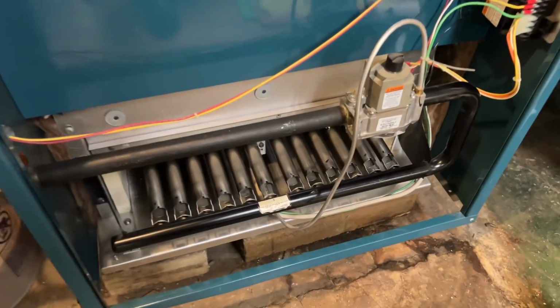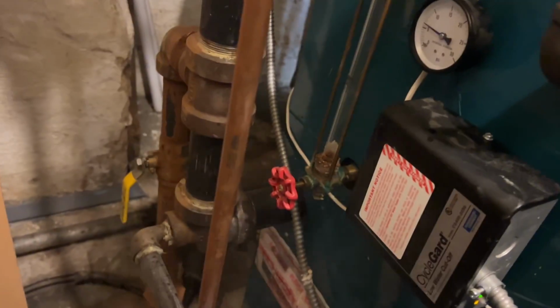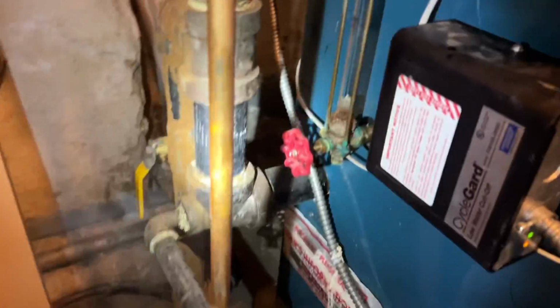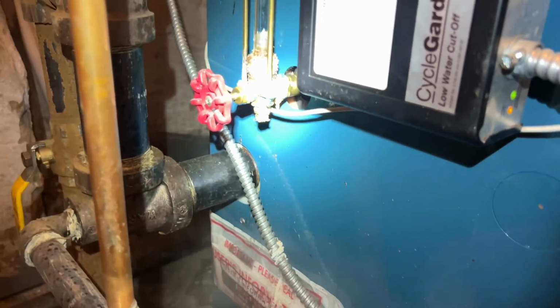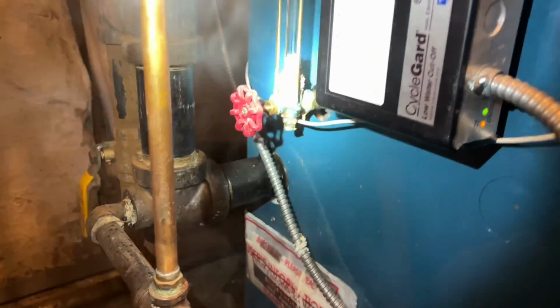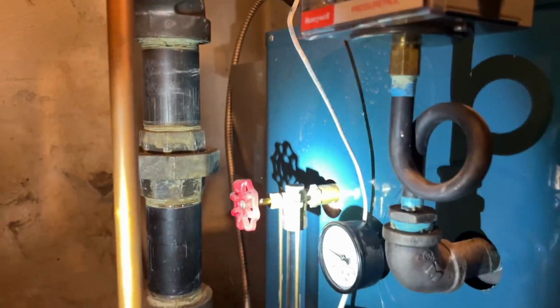All right, now that Peter has all of the burner tubes back in, I've reapplied power to the system, and we're almost done draining right there. I'm just getting a little more light right there so you guys can see. Almost done draining. This is bucket number 2. We are going to replace the sight glass nuts and washers on the bottom. We're going to use our wire brush and try to clean up all the corrosion and oxidization on the actual lower valve. Upper valve looks brand new, looks perfect.